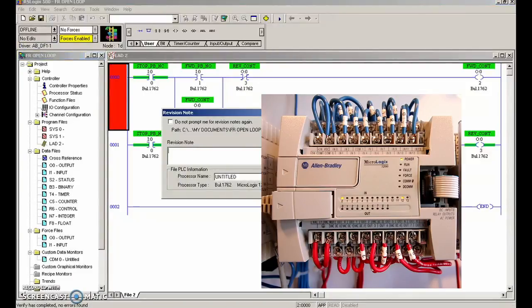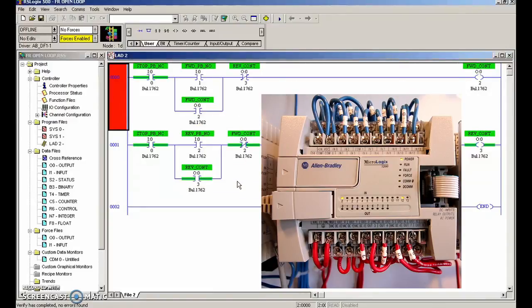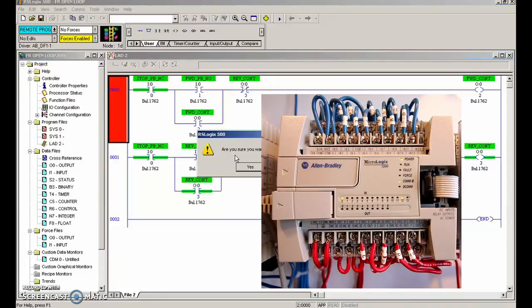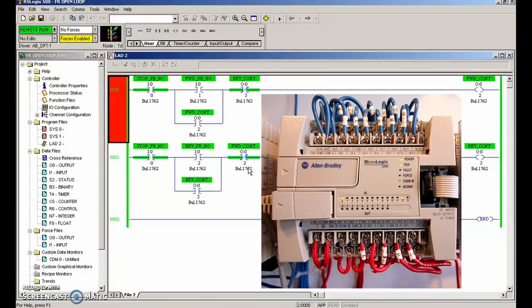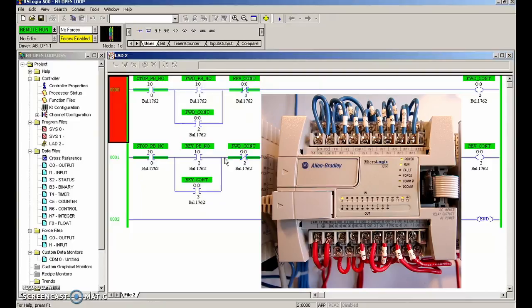Let's download that and make sure everything is cool. Again it's bumping into remote program, so I'll put it into run. Beautiful — hit the forward push button, contactor turns on, stop, reverse, stop. Everything's working fine with that open loop program. The next thing that's going to screw up your program is putting in the wrong address or the wrong instruction.